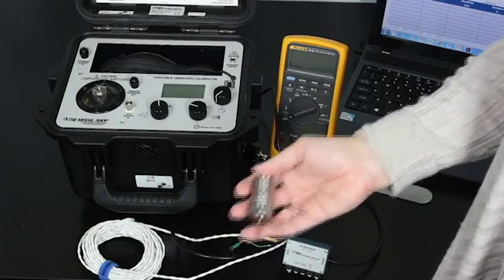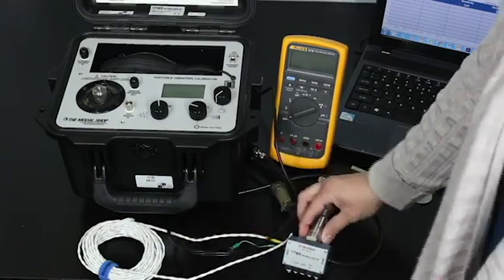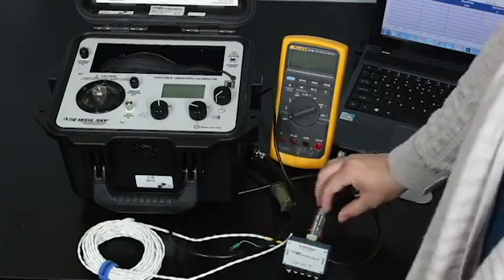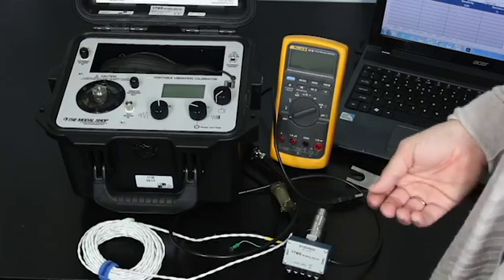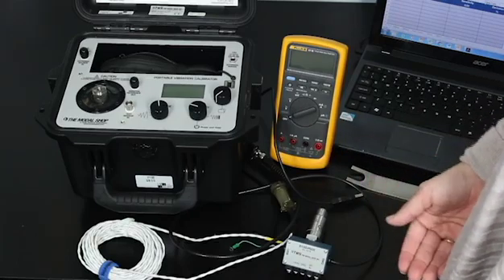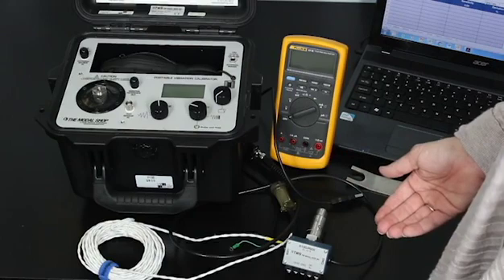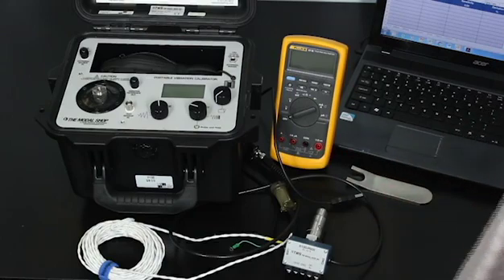When I talk about testing this type of sensor, what I'm really doing is confirming that the sensor's output is linear throughout its range and also that it reaches its full-scale output of 20 milliamps.